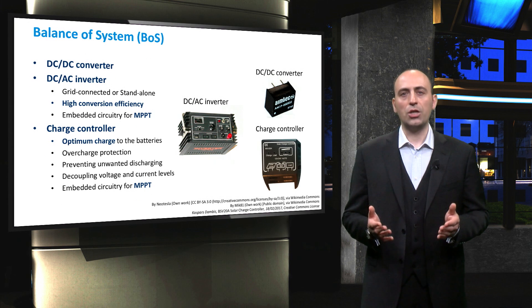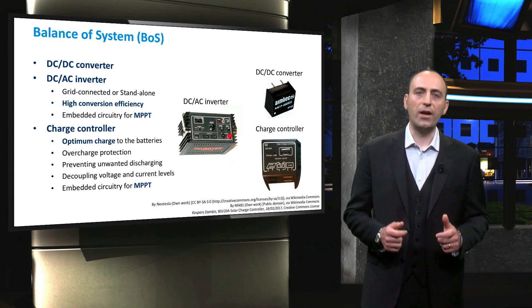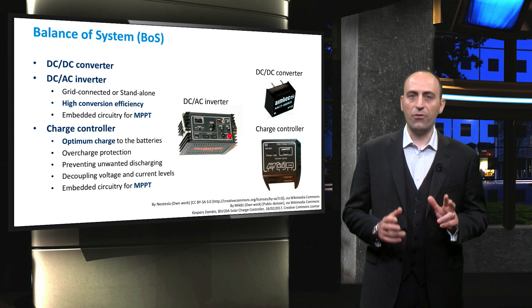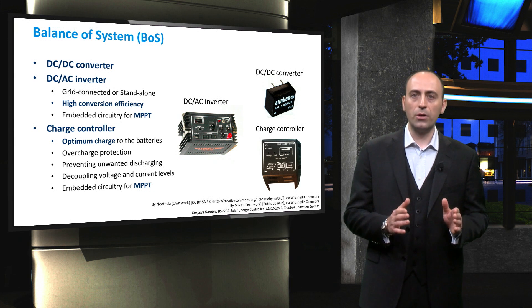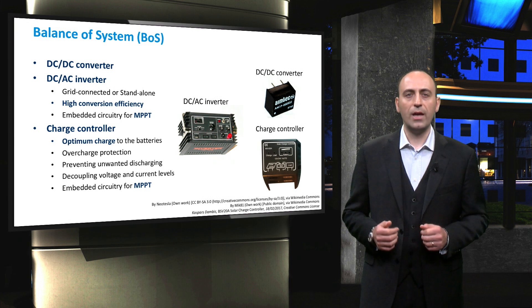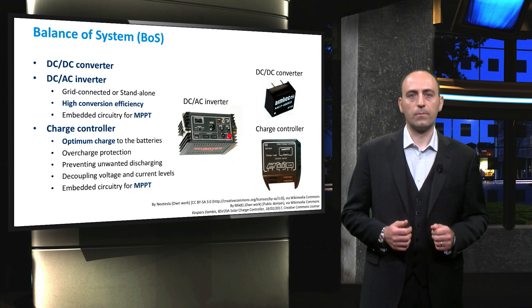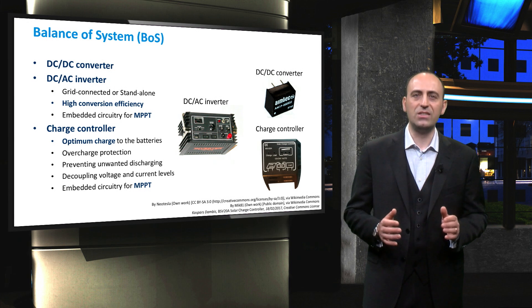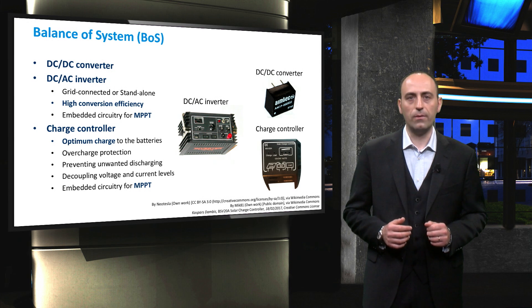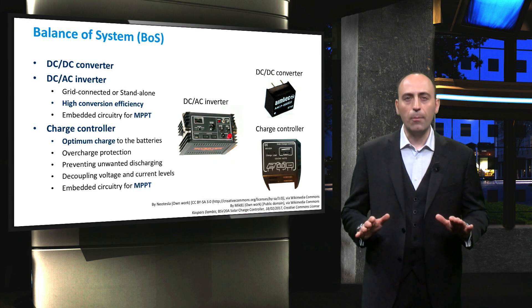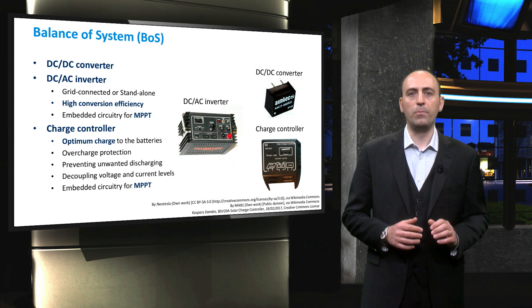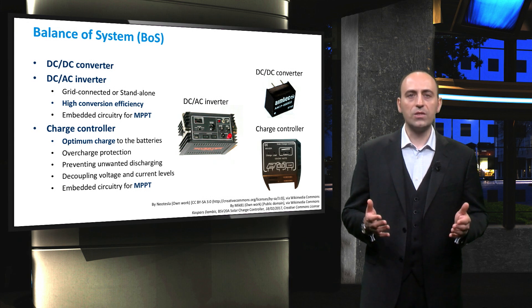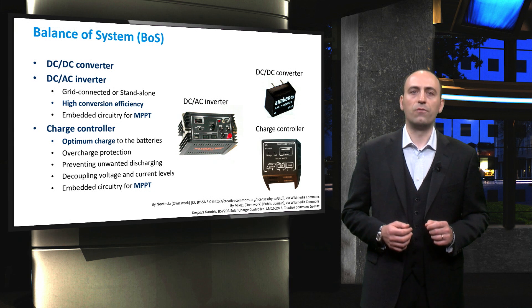Finally, the charge controller is used in PV systems to control charging and discharging of the battery. The charge controller is a three-port terminal. One port you plug the PV panels, on another the load, and on the third the batteries. Some models of charge controllers also contain a DC-DC converter alongside a maximum power point tracker. This is added to decouple the voltage and current of the PV modules from the voltage and current of the battery bank. In this way, we can always obtain the maximum power from the modules.